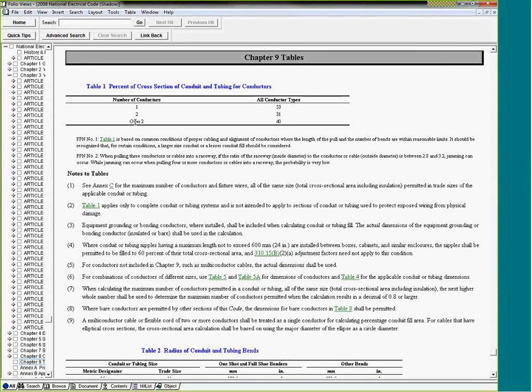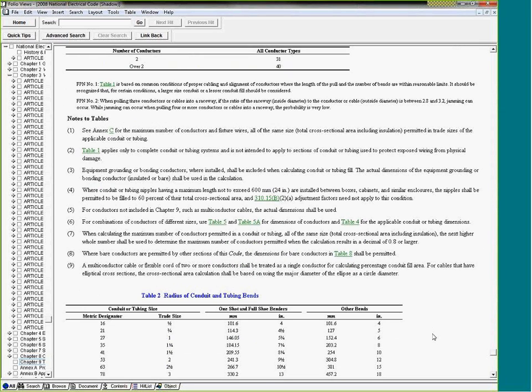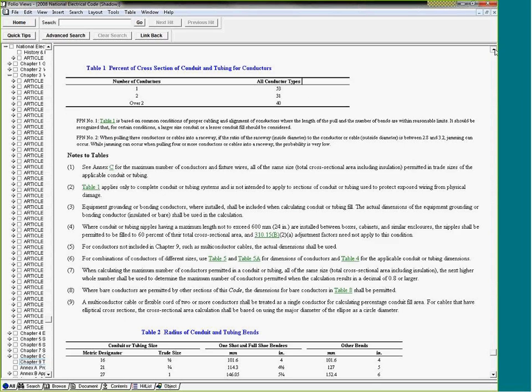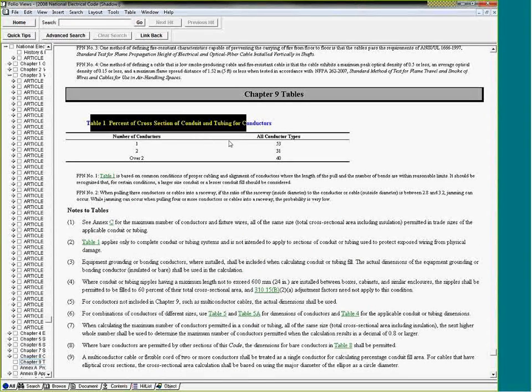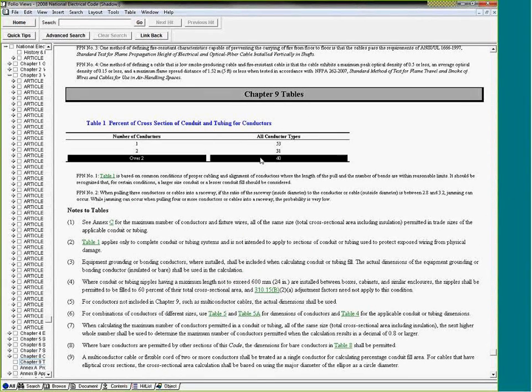Okay, so for sizing conductors, here's what that table keeps saying. Go to Table 1. It will tell you if you have more than 2 conductors, you can't fill more than 40%. Remember, with 2 conductors, 31%. If you have 1 conductor or cable, 53%. So that's a very interesting one here.